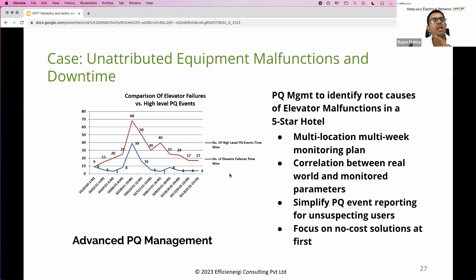You see the strong correlation which came out over a period of almost 2 months with 5 analyzers deployed at multiple locations. We could solve this problem without almost a dime of investment by the customer, with a simple tap changing of their OLTC, which was undertaken, not the OLTC, sorry, the offline tap changer, and 70% of these problems disappear. That's the beauty of going for an in-depth power quality management or monitoring study, which throws up all of these correlations which are never so quite visible. The elevator manufacturer had just told them it's a problem due to mechanical failure or drive failure. They used to replace cards and so on and so forth.